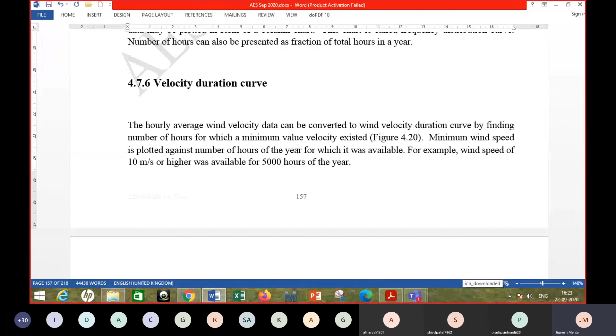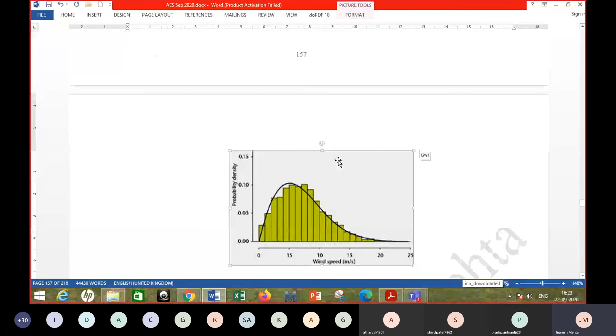Then I may talk about 2 meter per second. Let's say it was 60 hours for 0 to 1 and 200 hours for 1 to 2, right? So for 260 hours it was less than 2 meter per second, and for the remaining 8500 hours it was 2 meter per second or higher. That way you can tabulate the data and present it as velocity versus the number of hours for which that minimum velocity was available. In that case, we will draw a graph like this.